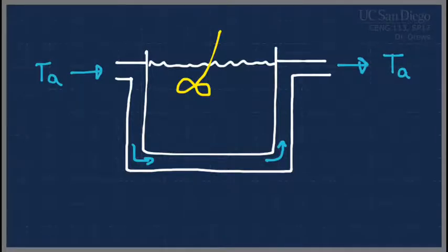Not that uncommon for a smaller reactor. The bigger the reactor gets, the harder it is for a jacket like that to affect the temperature in the middle of the reactor. So you have to stir the thing really well. You have to put baffles and stuff inside there to try to keep that temperature constant inside. It's really easy to get what are called hot spots with something like this, where the fluid, no matter how well I mix it, tends to slow down when it's over here in the corners. So it might be plenty fast elsewhere, especially around the actual mixer, but there can be dead zones in there, and those can get very, very hot.